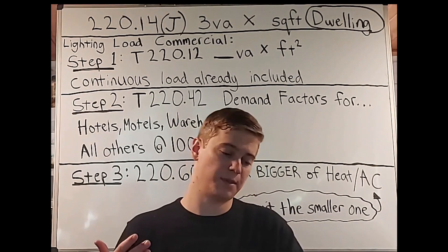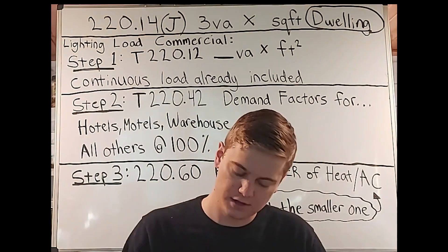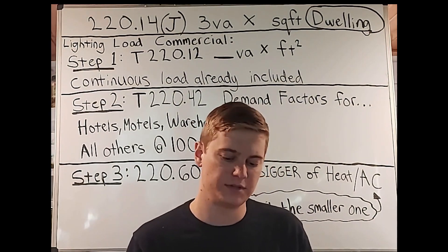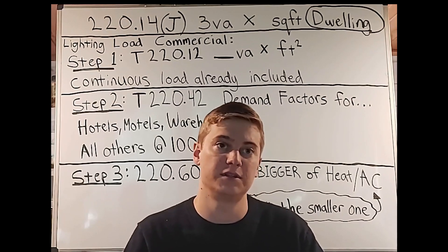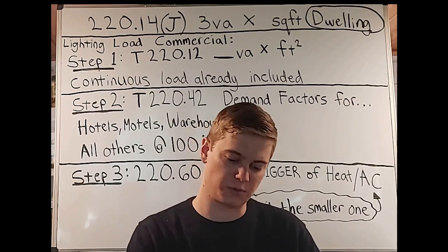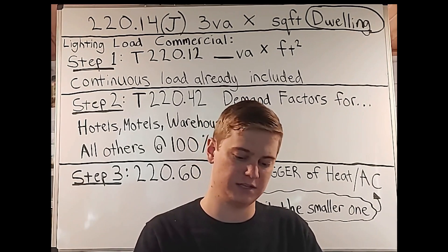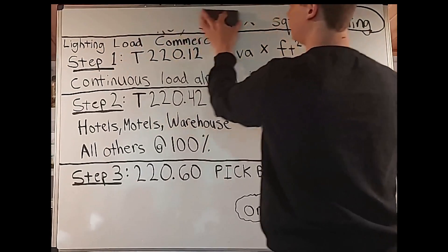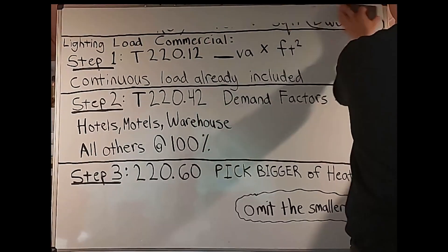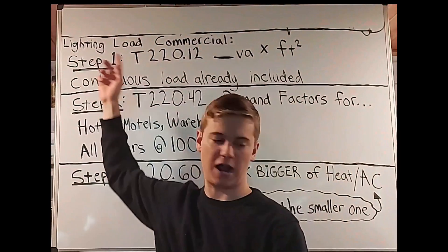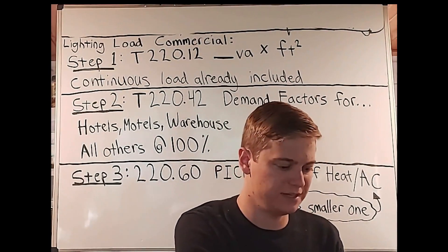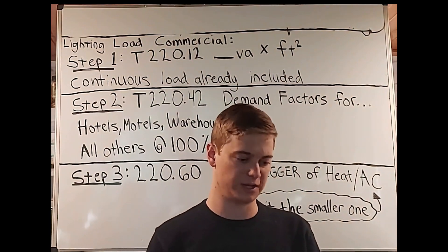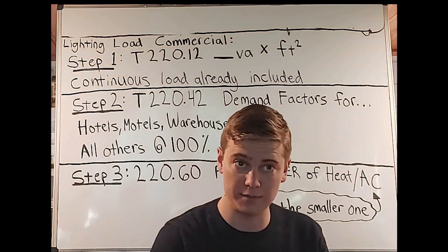This first one we know from the past — 220.14J — where it says dwelling units. This obviously doesn't apply here, but this is where we see the three volt amps per square foot. We're not going to use that unless we're dealing with dwelling units. Instead, for our lighting load, we're going to use article 220.12, lighting load for non-dwelling occupancies, which also has a table that accommodates this.